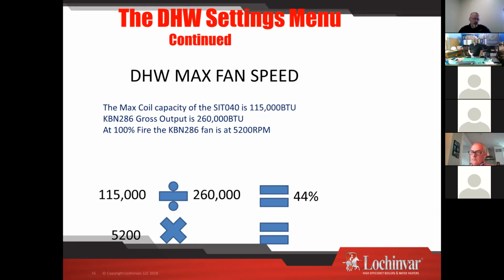So 5,200 RPMs is the maximum fan speed of that boiler, which you can find by going into the actual domestic hot water settings, and the boiler will tell you what its maximum fan speed is. You do the math, it comes out to 2,288 RPMs is what you're looking for, and you would actually go in there and set that maximum fan speed to 2,300 RPMs. And on a call for domestic hot water, that's as much boiler as you're going to fire, and that's going to keep that boiler from overfiring and being unable to really dump the energy.